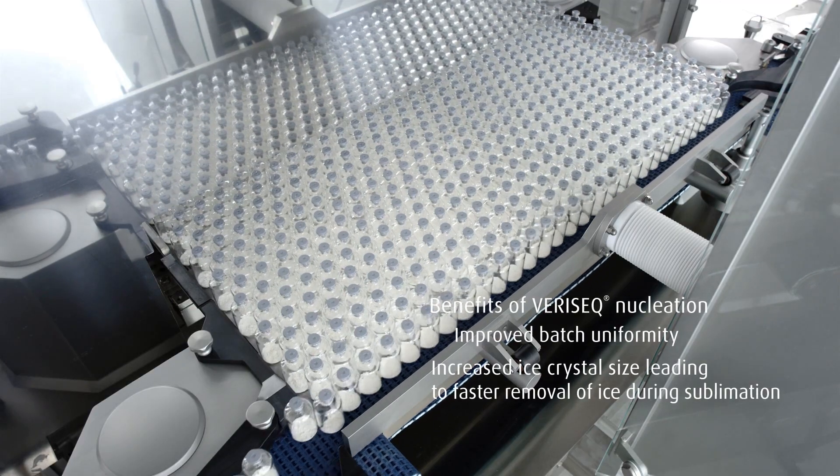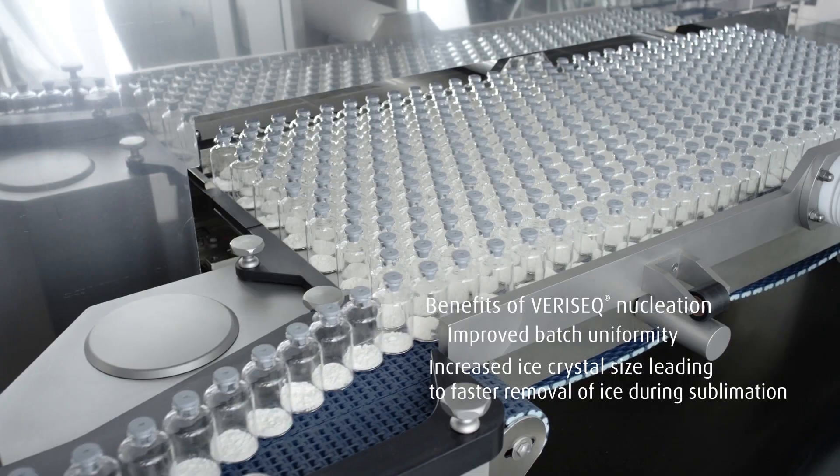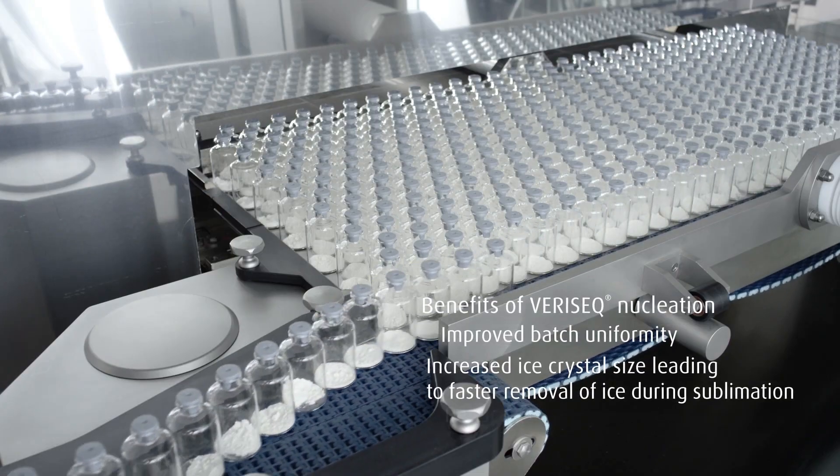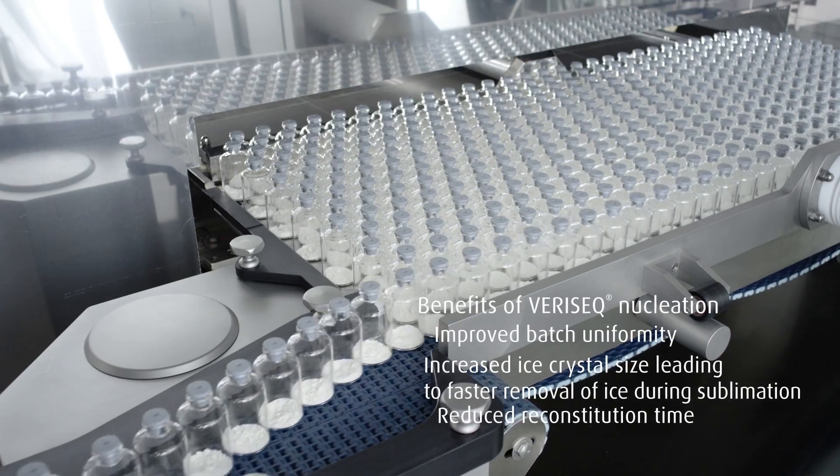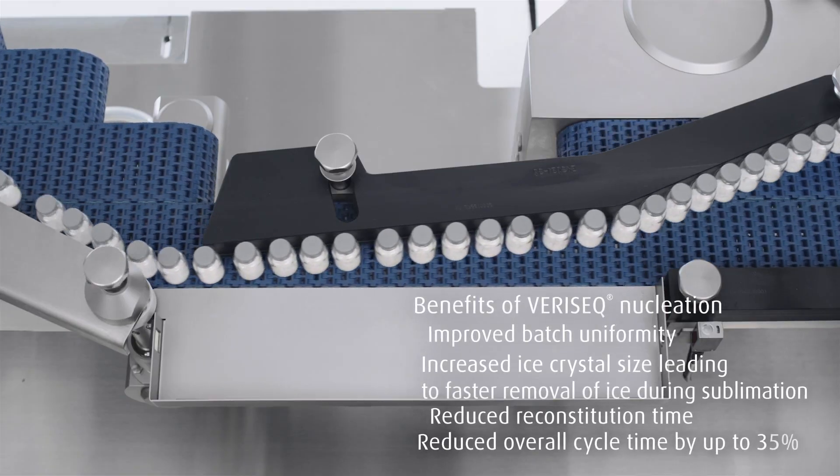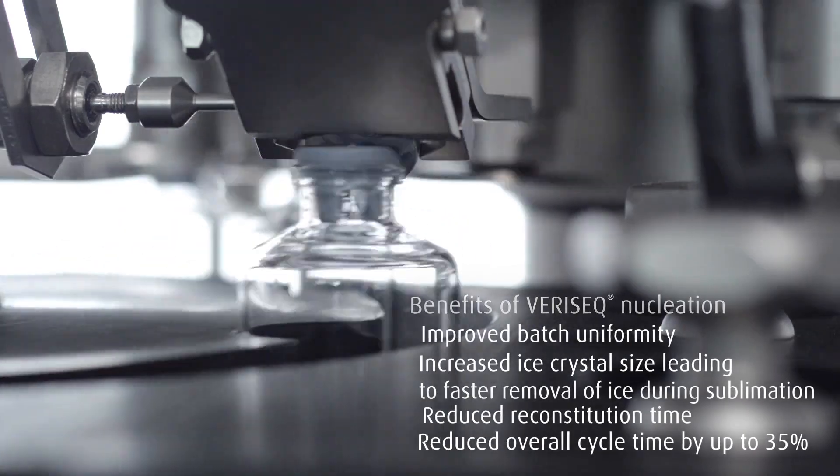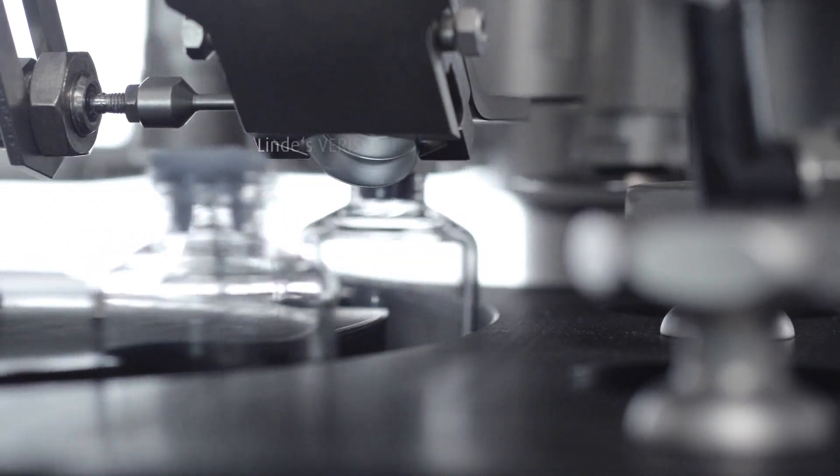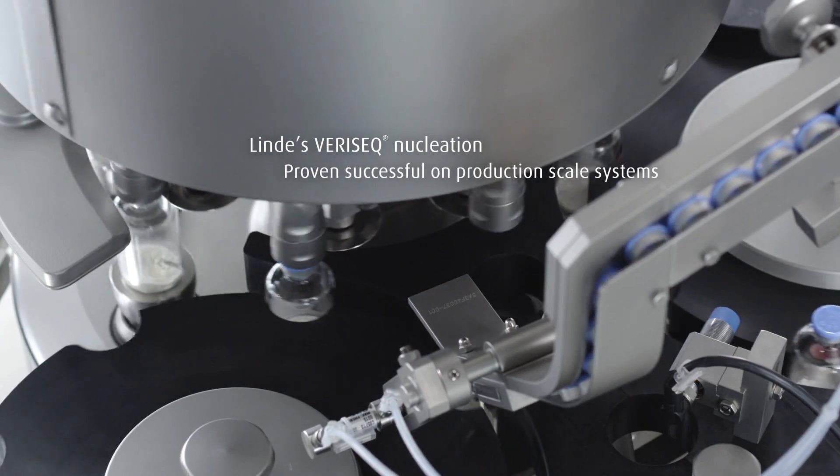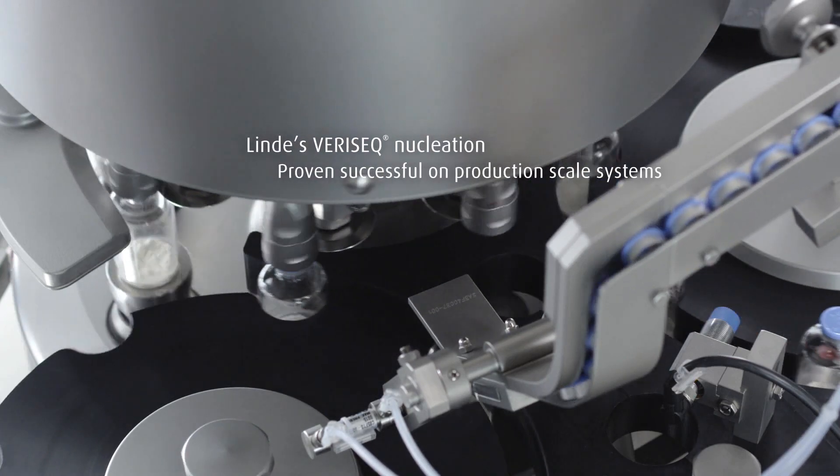Ice crystal size is increased which leads to faster removal of ice during sublimation and shorter reconstitution time. Overall cycle time can therefore be reduced by up to 35%. Linde's VERISEQ nucleation has been tested and proven successful on multiple lab and production scale systems.